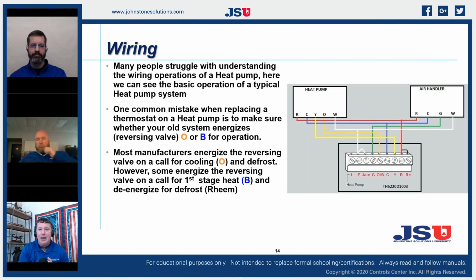So in our history of heat pumps, we have had two different philosophies of the manufacturing of our outdoor unit. One has decided that if I have a failure of my solenoid, or a failure of some wiring going to my reversing valve, I would like the steady state, or the natural state, of my outdoor unit to be in heating mode if I have a failure. The other part of our industry has decided, well, we would rather the safe mode be cooling for our outdoor unit. I still don't understand that philosophy. I could go without cooling, but I'm not going to do very well without heating, right?